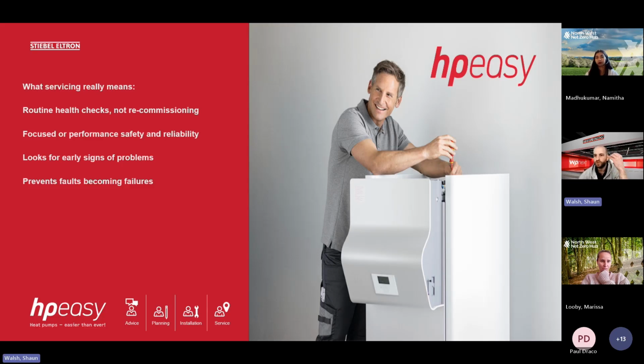So quickly just go to what most service actions are on a typical day. Most of them are just a visual check of the system. So you're visually checking the system to make sure that there's no corrosion of any components, any leaks, any sort of damage to any of the system components, and cleaning the air source heat pump if it's an air source heat pump. With an air source heat pump, actually, the machine outside doesn't need a lot of taking care of. It's the actual system inside that needs most of the attention.